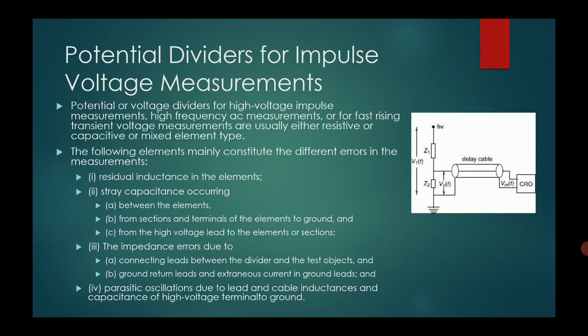The following elements mainly constitute the different errors in the measurements: the residual inductance of the elements; the stray capacitance, occurring between the elements, from sections and terminals of the element to ground, and from a high voltage lead to the elements or sections; the impedance errors due to the connection between the dividers and the test objects, the ground return leads and extraneous currents in ground leads; and the parasitic oscillation due to the lead and cable inductance and the capacitance of the high voltage terminal to ground. All these factors contribute to the different errors in the measurements.